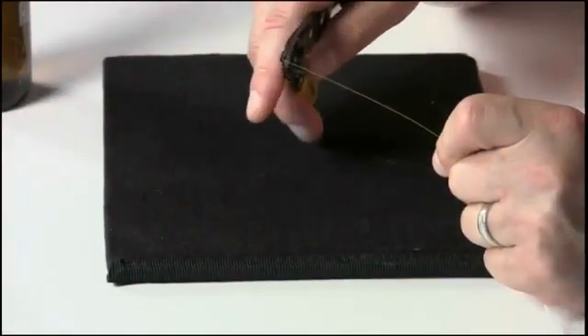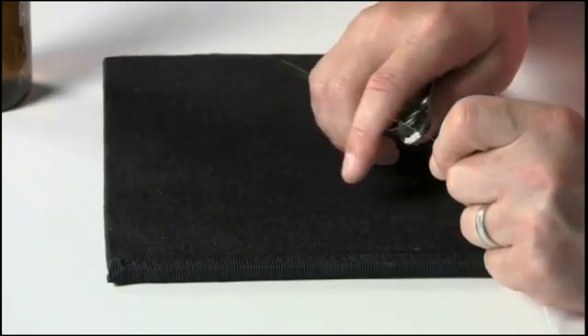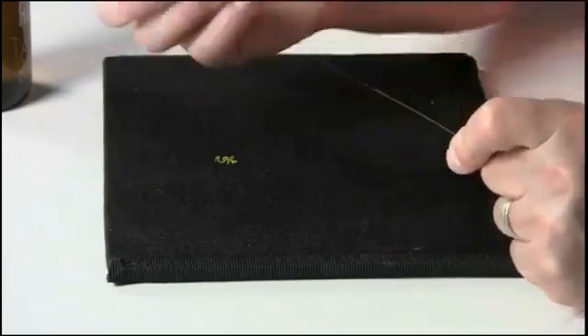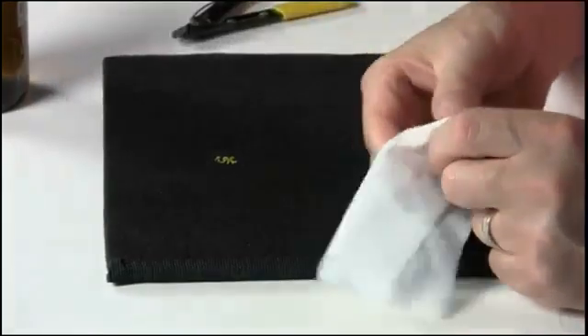You would strip the cable approximately 30 mm. You need to ensure that all of the acrylate is off of the fiber cable itself. And when that is done, you use 95% or better alcohol and you clean the fiber.